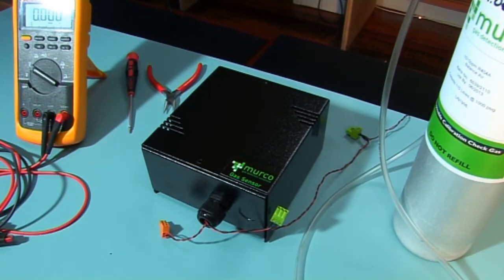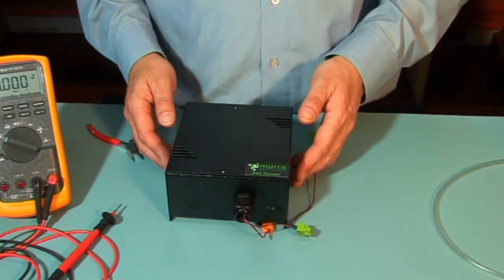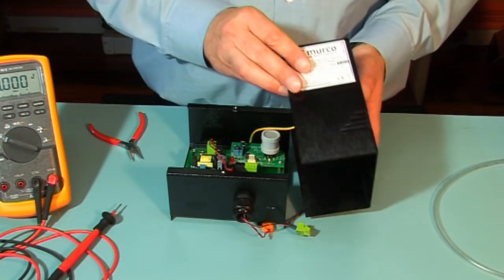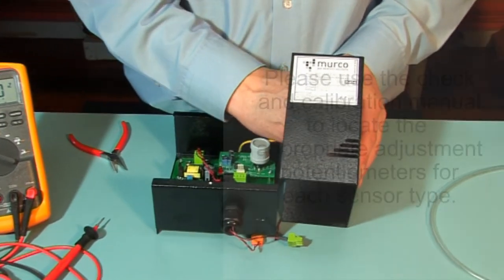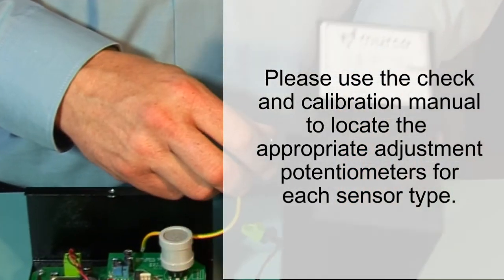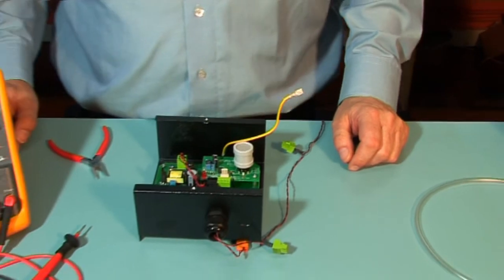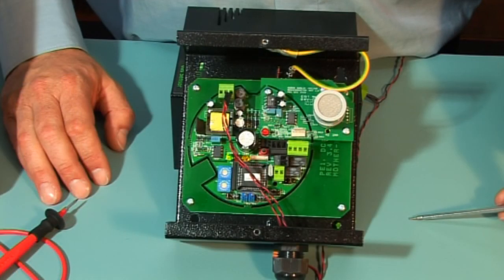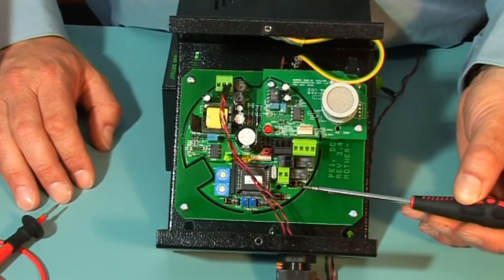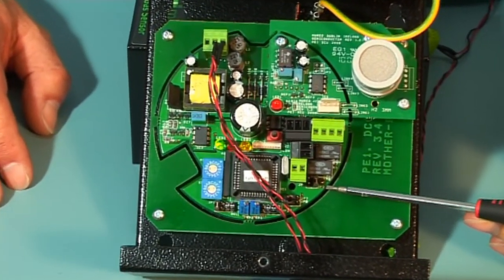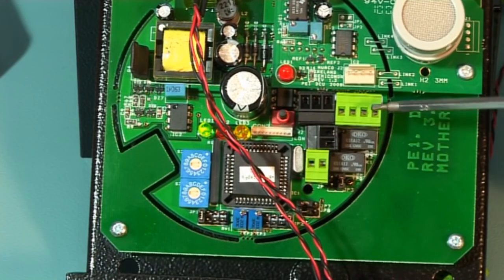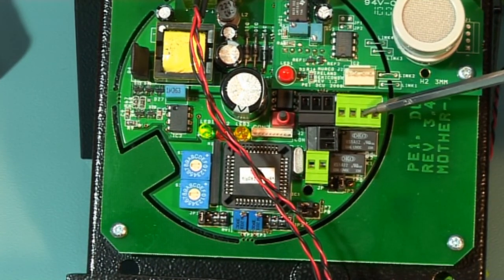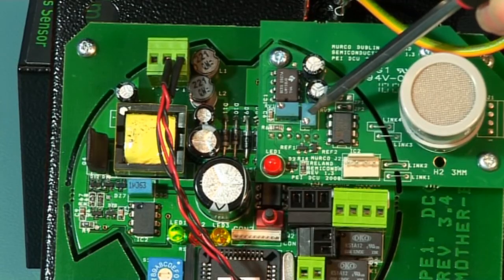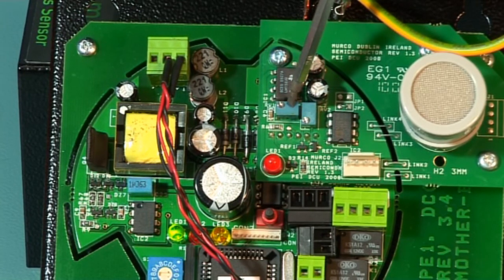For demonstration purposes we will be using the semi-conductor model, but the procedure is the same for all ST-IAM models. Please use the check and calibration manual for the appropriate adjustment of potentiometers for each sensor type. The 0 volt test is marked here on the motherboard as TP0. The sensor voltage output in clean air is monitored at pin 3 on CON3. The adjustment for the 0 voltage is RV2 and the span or range adjustment is RV1.